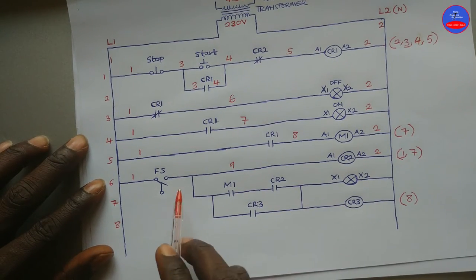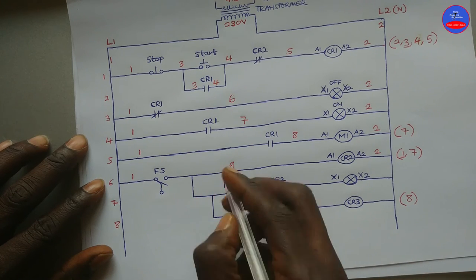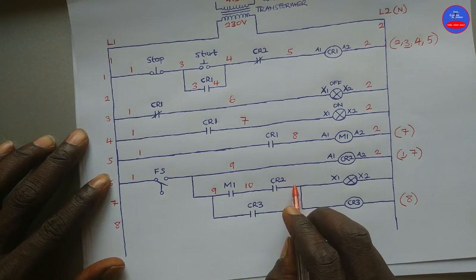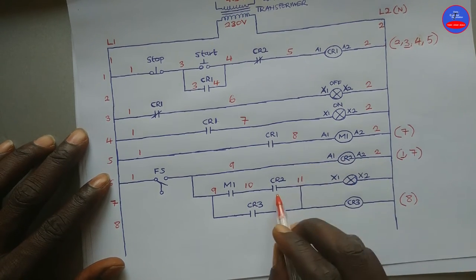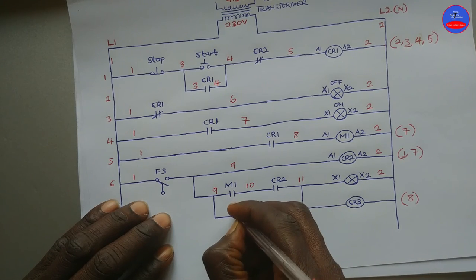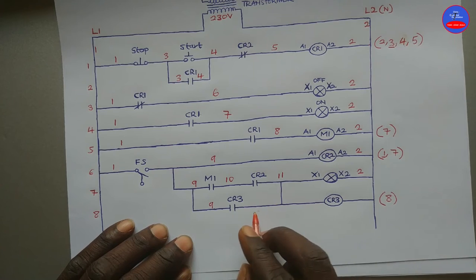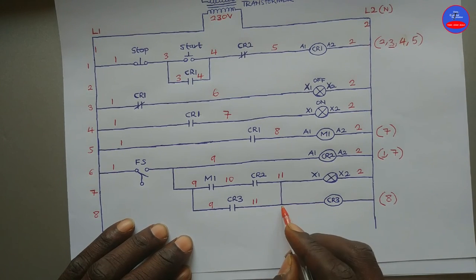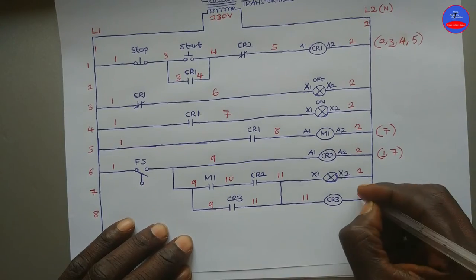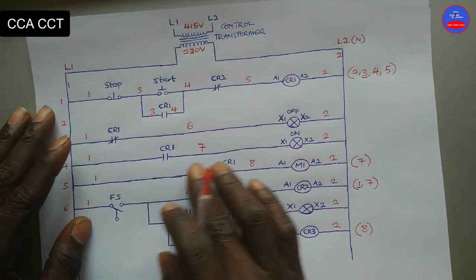We tap from three to one side of the open contact — that side is three. We tap from four on the start button — that side is four. Continuing down: line one side is one, the next new wire is six, then seven, eight, nine, ten, eleven. Where wires branch from the same node, they share the same number — so tapped points from nine remain nine, and tapped points from eleven remain eleven.